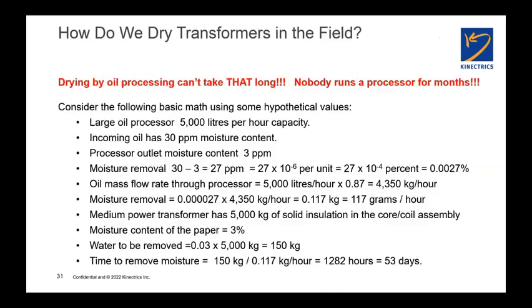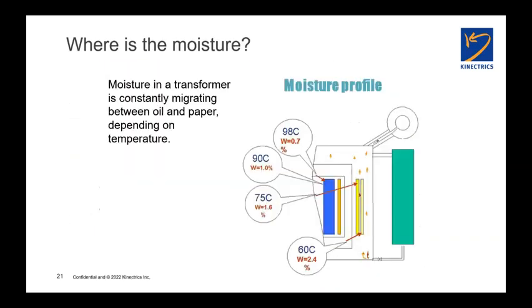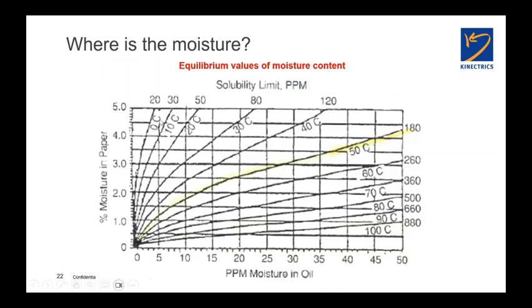And again, if I can just back up to further that, if I go back to my Oommen curve, look at what happens at 0 degrees C, 10 degrees C, even 20, which is room temperature. These lines are approaching almost a vertical line. And so a very, very slight difference in parts per million content of the oil has a massive impact on using this curve to infer the moisture content of the paper. So if you start to get down below 20, you've got to be really careful in interpreting the results.